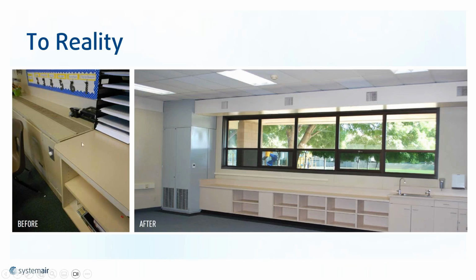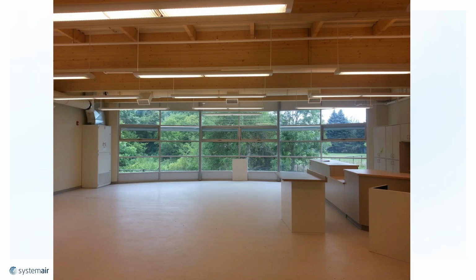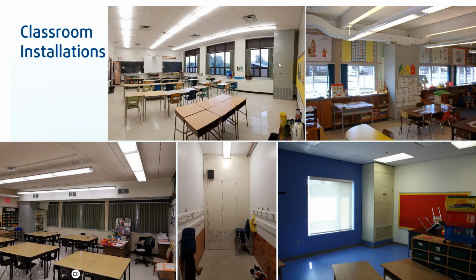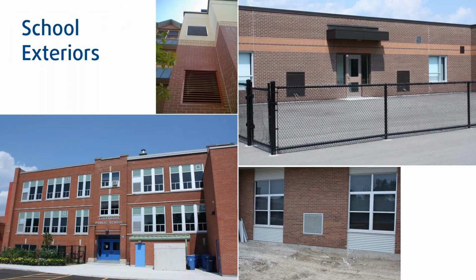The next slide just shows a traditional horizontal, old school mounted unit ventilator, and then upgraded to what I call the 21st century classroom air handler, the 21st century vertical unit ventilator, right? So the best thing is they just take the horizontal unit out and they put cabinetry, and then they duct from the top. And again, just some typical examples of classroom installations. You see it there, you see it there. When we calculate the square footage, it takes about 2% of the actual square footage of an average classroom. Louvers, right, complement the unit or are necessary, but we could change those to two main colors. You get a bronze finish and a gray finish.